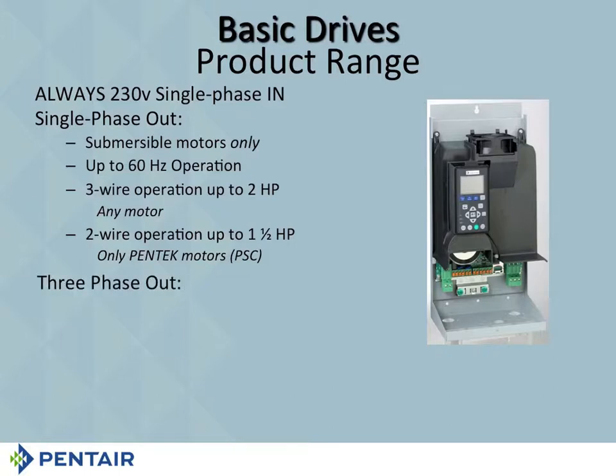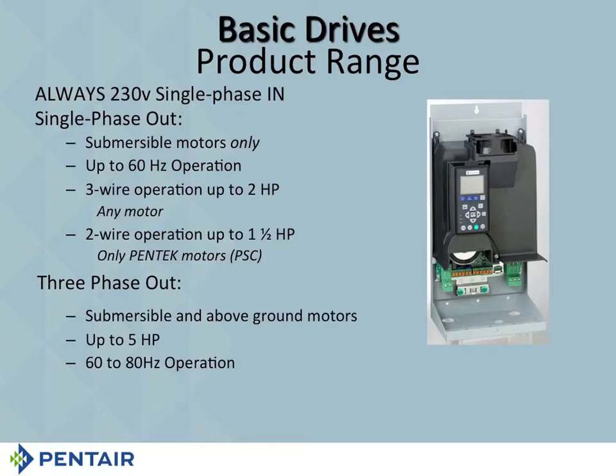You can do three-phase out, and if you do, you can use it for submersibles or above grounds. So that's kind of nice, submersibles or above grounds. Up to 5 horsepower, and of course, we're going to recommend 60 hertz, but we've got the drive set up so that if someone else has already put in one of these 80 hertz drives, they can take the other competitor's drive out, put our drive in, and still leave that 80 hertz pump and motor in the well. We won't make them take that out of the well.